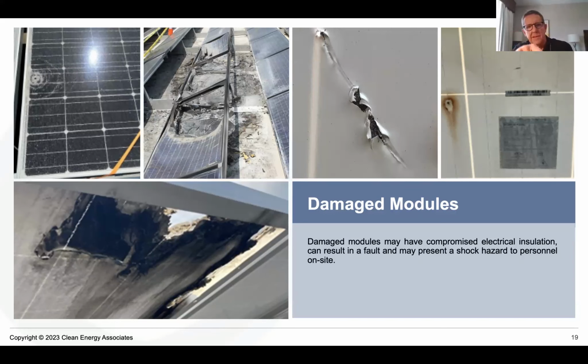That picture on the left where the fire damage is on top, that's from backsheet scratches caused by mishandling, which could have been avoided by pulling those scratched modules and replacing them. You wouldn't have had the downtime and the damage. On this project, that damage was a good $40,000 to $50,000 worth of fixing.